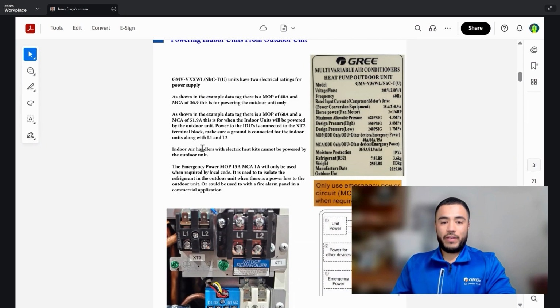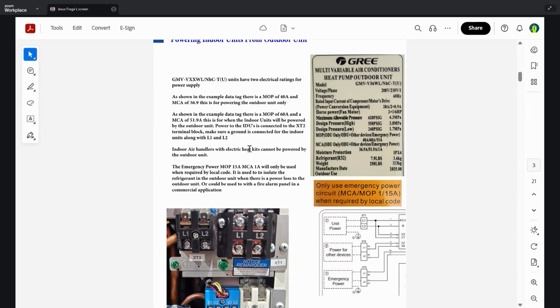So if any of the indoor units do have heat kits, please use a dedicated line of power from the panel. That way you don't run into any problems with inspectors. The emergency power MOP is 15 amps, MCA is 1, and it will only be used when required by local code. It is used to isolate the refrigerant in the outdoor unit when there is a power loss to the outdoor unit, or it could be used with a fire alarm panel in a commercial application. So that was having to do with emergency power.